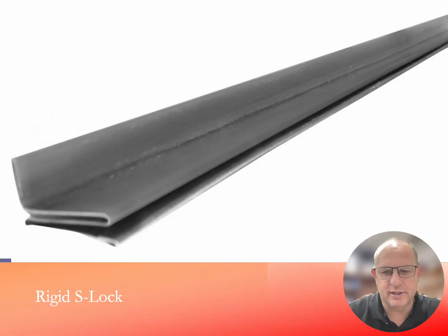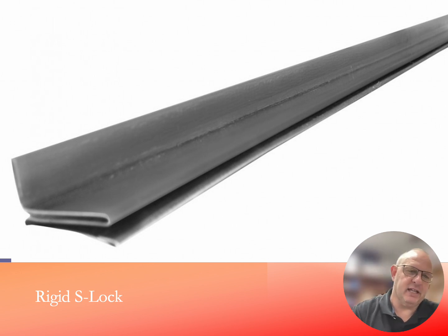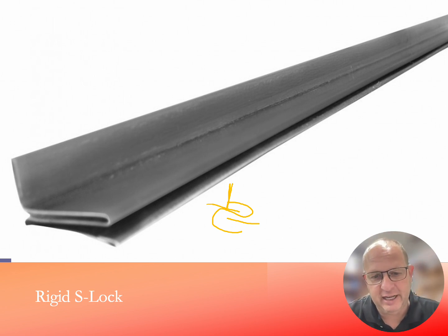Well, some of the different types of connectors that you will find on your systems. We talked about the S-Lock. Well, this is a lot like the S-Lock. This is called a standing seam S-Lock. You take that S-Lock where the two pieces of metal are going to fit in between it, and we add a seam to that S-Lock. What this is going to do for us is add rigidity to the ductwork itself. It's going to add strength. I like using this standing seam when I'm trying to hang piping or ductwork. It just gives it something to go across that gives it a little bit more strength than what that original S-Lock would give us. Another term that we use for this is rigid S-Lock or standing seam S-Lock itself.